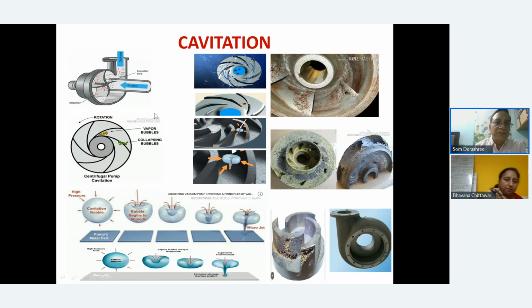Now you see, I have the impeller. You have suction coming in, and then there will be a change in direction. A lot of losses will be happening in the impeller as it changes direction. Now what happens is, supposing your bubble forms. These are all pictures of cavitation implications. This is the whole metal; see how much hard metal has gone away.